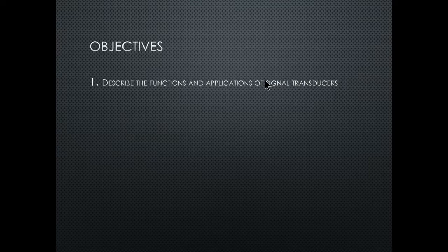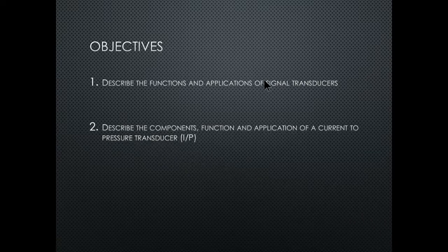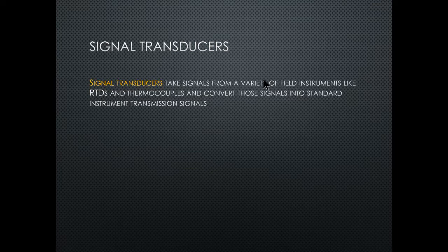The objectives for this lesson are to describe the function and applications of signal transducers — this is mostly what the ILM is about — and to describe the components, function, and application of a current-to-pressure transducer, called an I to P. Signal transducers take signals from a variety of field instruments like RTDs and thermocouples and convert them into standard instrument transmission signals.